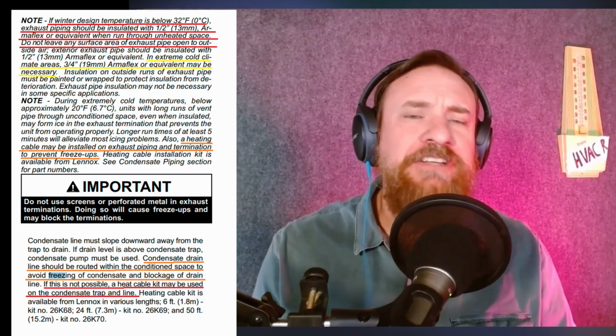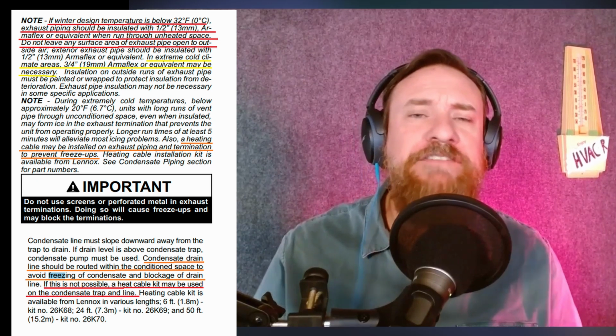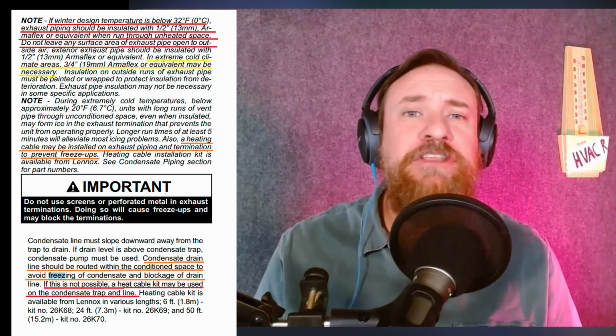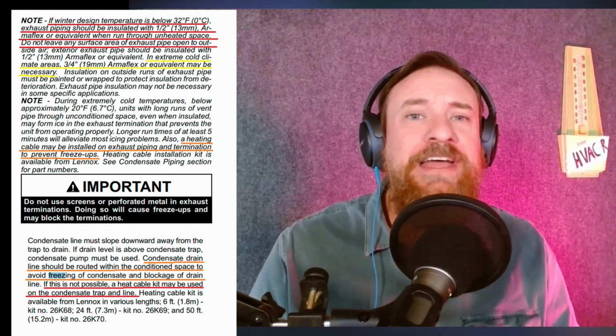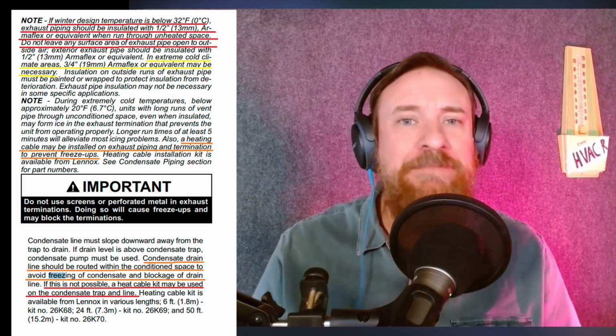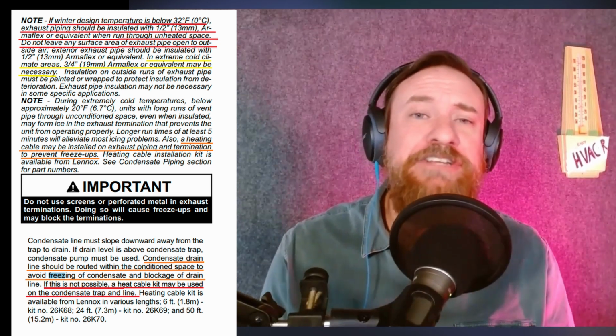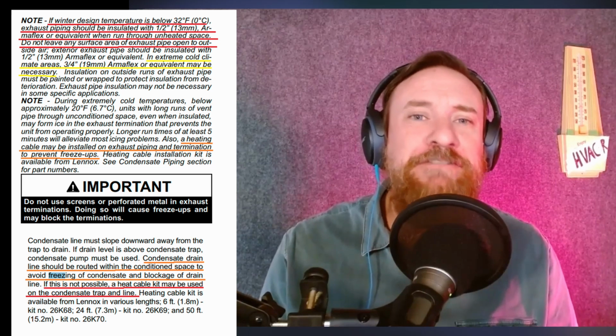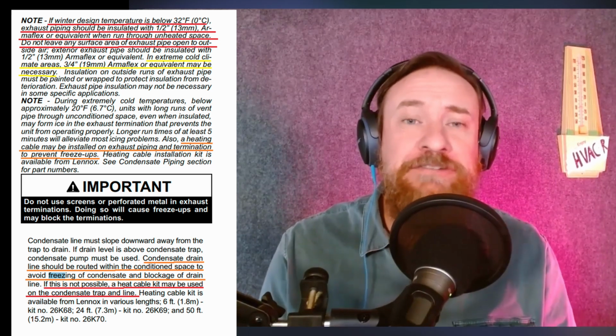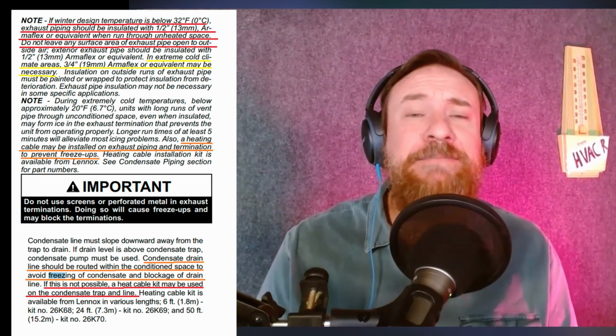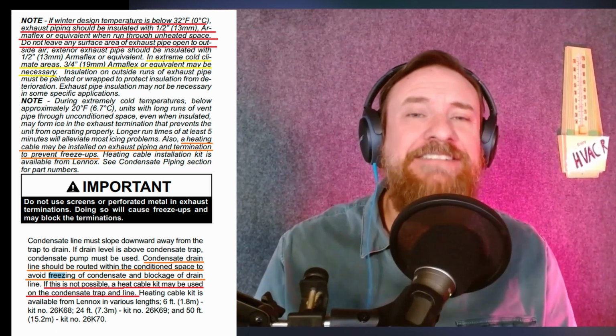If it's going to be installed in an area below 32 degrees, you have to install freeze protection. In other words, the drain line has to be wrapped with heating tape, that tape that keeps the pipe warm so the drain can continuously drain. You must also have the flue pipe insulated if it's going to run through a space that's below 32 degrees.